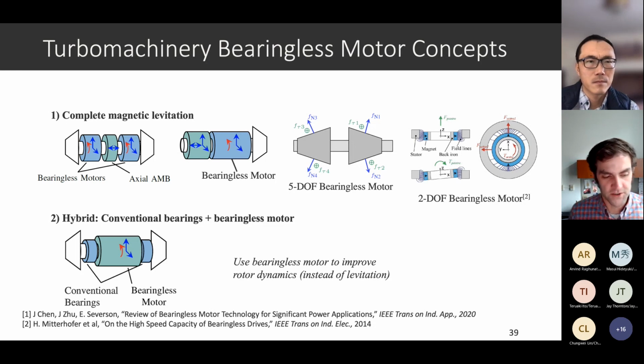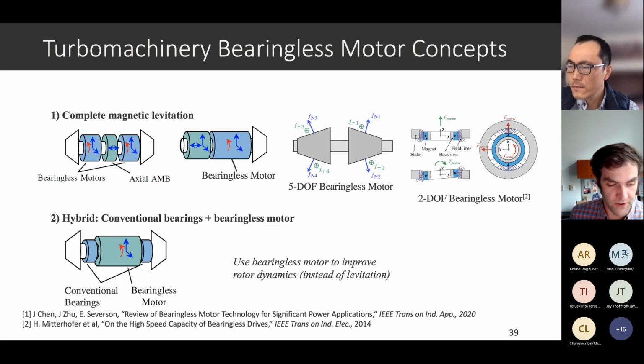Also, the magnetic bearing gives you a handle of controllability, so you can change and tune your dynamic stiffness on the run, without it being just a fixed design-time issue. The drawbacks, of course, are that with magnetic bearings there are lots of sensors, lots of electronics, and more capital cost compared to air bearings. The other thing of note is that air bearings don't work in applications where you don't have air, right? If you're in a vacuum environment, the air bearing isn't going to go. HVAC chiller compressors are a harder story as well. Interesting answer. Okay, thanks.